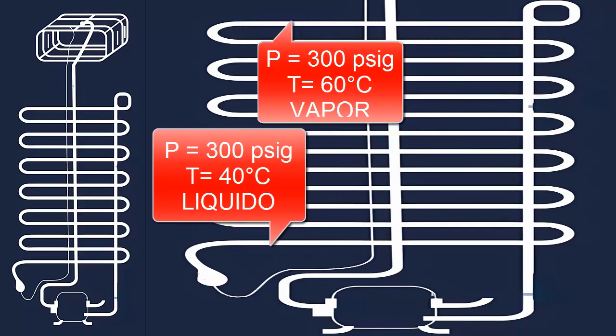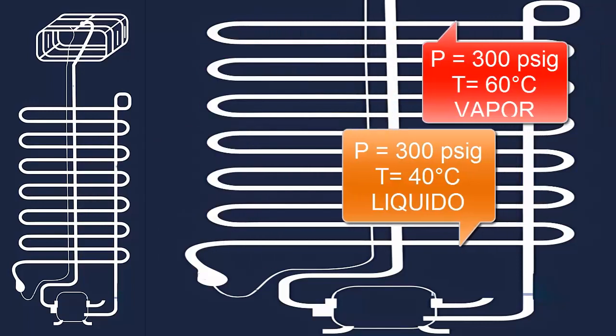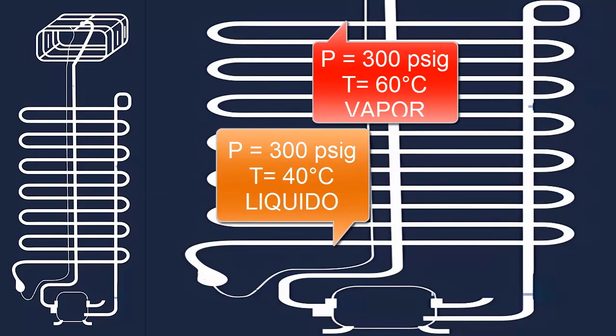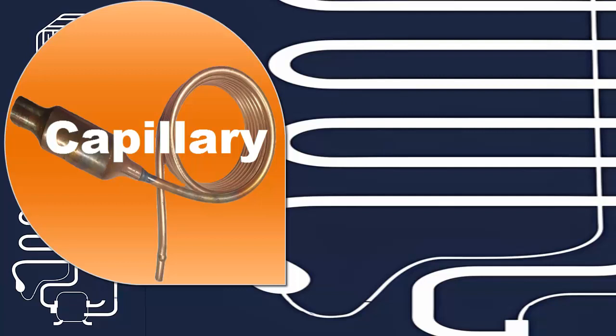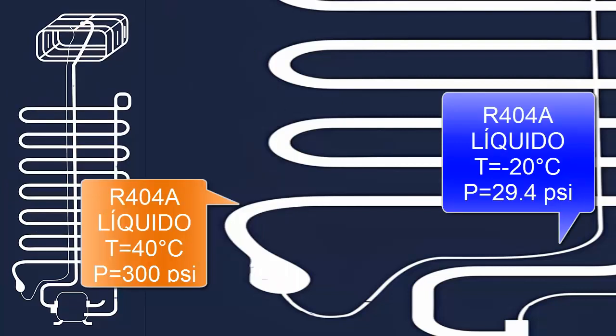The R404A, now in a liquid state and at a temperature close to the ambient, exits the condenser and heads to the capillary tube to restart the cycle. In the capillary tube, the pressure and temperature of the refrigerant decrease considerably, so it returns to the initial pressure of 29.4 pounds per square inch and minus 20 degrees Celsius, restarting the refrigeration cycle.